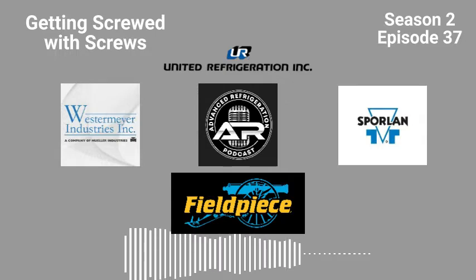And I started loosening up the cartridge, the screw compressor cartridge for the main oil filter, and ended up shutting the rack down. I'm like, you know what? Let's just shut the rack down. These ball valves are 20 years old. They probably are leaking through a little bit. So shut the rack down and I got it about halfway off and I start rocking it back and forth a little bit, get it to start leaking out oil. It stops about 5 minutes after doing that. I loosen up a little bit more, oil comes out. So I'm like, you know what? I'll give it 10 minutes. I rock it back and forth, nothing comes out. Well, evidently somebody double O-ringed this thing.